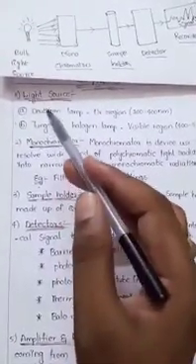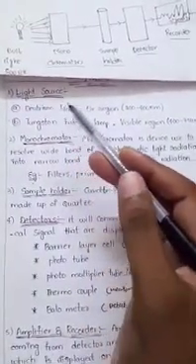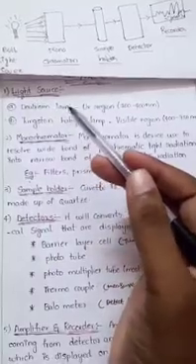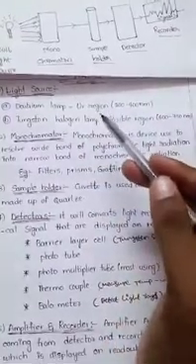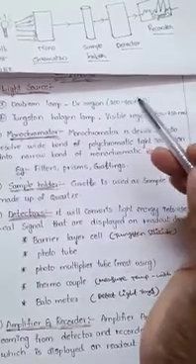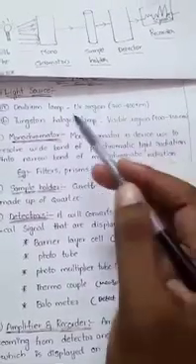See the parts explanation. The first part is the light source. There are two different light sources used in UV visible spectroscopy. The first one is the deuterium lamp, which covers the UV region — 200 to 400 nanometers. UV region means ultraviolet region. The second one is the tungsten halogen lamp.